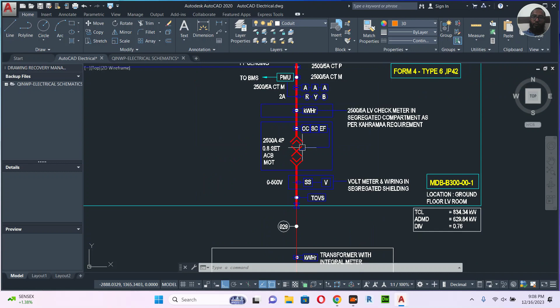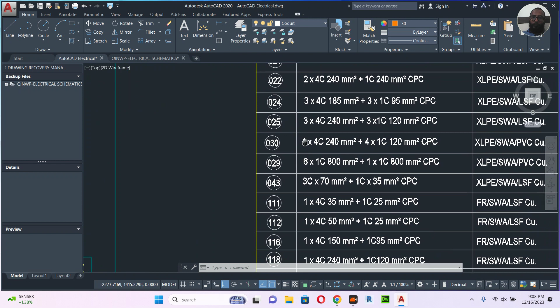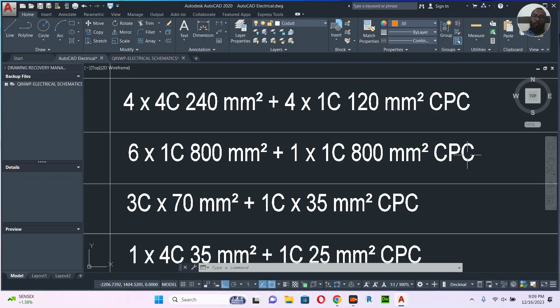So here the transformer connects to the breaker. This is a 2500 ampere 4 pole breaker. So you see here 029, and they have provided in the cable list 29 meaning. So this one is 6 by 1 core 800. As I told you before, actually it's a 7 run, 6 core, 1 core by 800 mm, this is a different kind of cable.